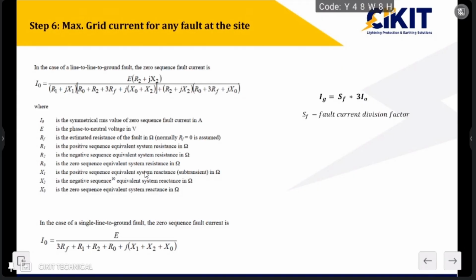So we are calculating this fault current, but we cannot ensure that the entire fault current will be flowing into the soil, because if I take one particular substation as an example, we have a lot of feeders and all the transmission lines come into the picture. If you take one particular transmission line, we will have a ground wire or shield wire on top of the transmission towers. This ground wire will also be connected to this particular earth mat. When any fault happens, the fault current will return to the source, and we consider that the return takes place through the soil, but it is not mandatory that all the fault current has to return to the source through the soil.